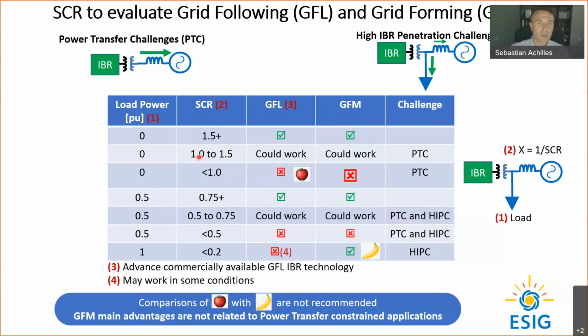If the short circuit ratio is between 1 and 1.5, this will be a really weak condition. Well, it kind of depends on the controls and some of the characteristics of the grid. Potentially, this could be made to work with both grid following and grid forming. Below short circuit ratio 1, it is not possible to have a steady state operation of a system like this. So it doesn't matter if you have grid following or grid forming, these types of conditions are unstable. So with grid forming, short circuit ratio slightly less than 1, it will be unstable, grid following the same.